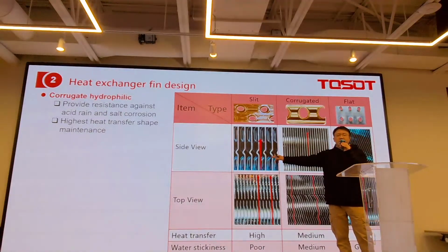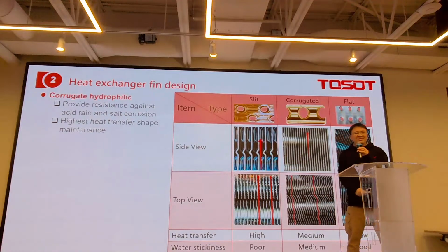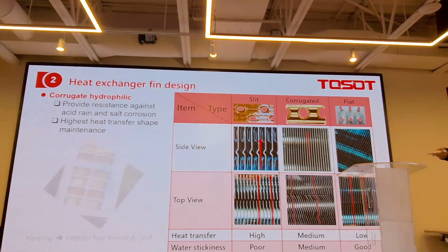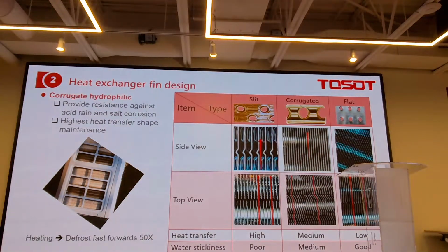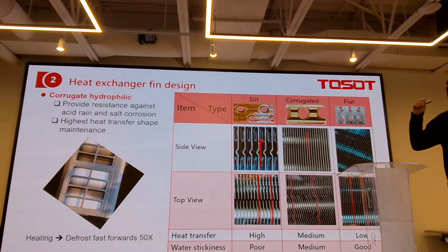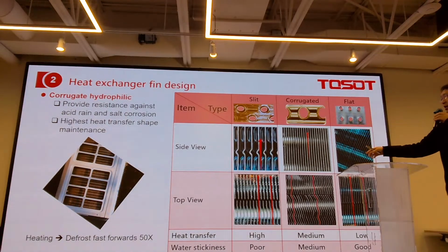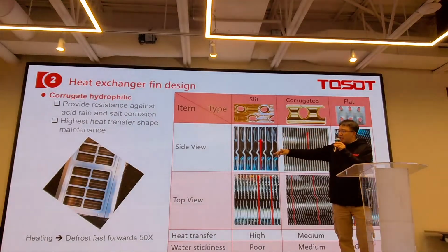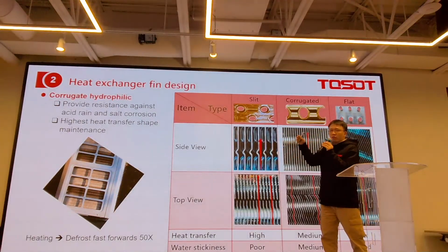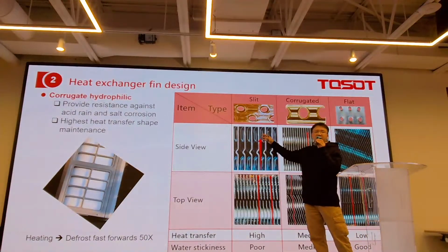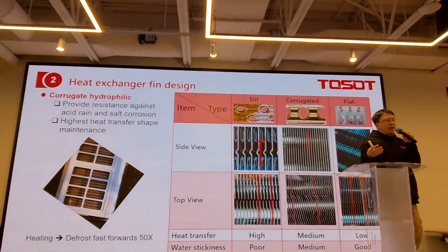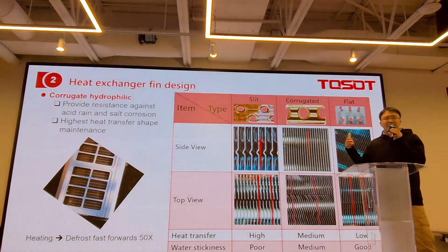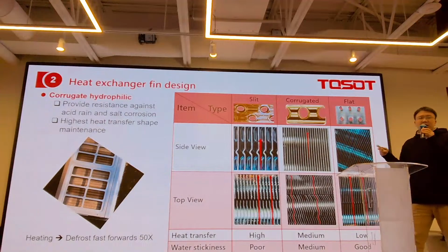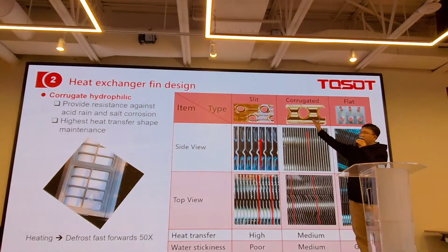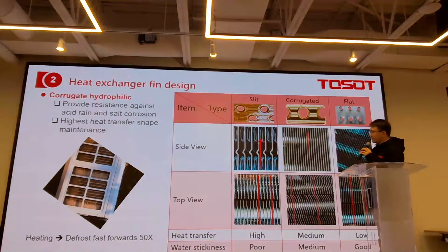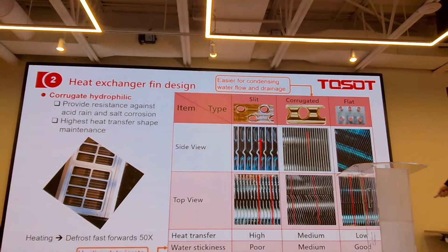However, this one has a disadvantage. Do you know what it is? Yeah, correct. Especially when the outdoor ambient is lower than the freezing point, it will easily form a lot of frost at the outdoor condenser, right? And then we need to defrost, which is to make the ice become water. However, during the defrost, the water can easily stick in these slits, which makes it difficult to flow out, and then it can easily become ice again in the next heating cycle. So from this comparison, we choose this corrugated fin instead of the slit fin. It's the outdoor condenser fin structure.